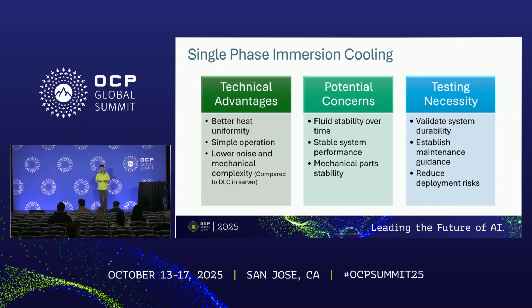For single-phase immersion cooling, there are a few technical advantages. First, it has better heat uniformity, meaning more uniform component temperature across the system. It's simpler to operate, has low noise, and lower mechanical complexity compared to DLC servers.